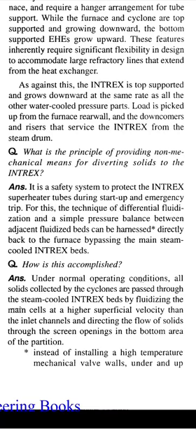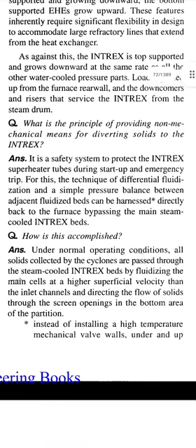Answer. It is a safety system to protect the Intrex superheater tubes during startup and emergency trip. For this, the technique of differential fluidization and a simple pressure balance between adjacent fluidized beds can be harnessed, directing solids directly back to the furnace, bypassing the steam-cooled Intrex beds. Question: how is this accomplished?